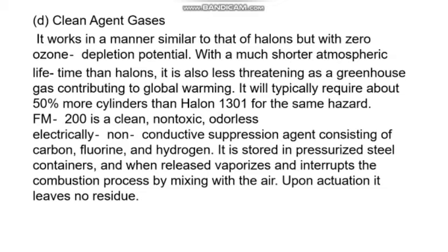One example of clean agent gases is FM200. It is a clean, non-toxic, odorless, electrically non-conductive suppression agent consisting of carbon, fluorine, and hydrogen. It is stored in pressurized steel containers and when released vaporizes and interrupts the combustion process by mixing with the air. Upon actuation, it leaves no residue.